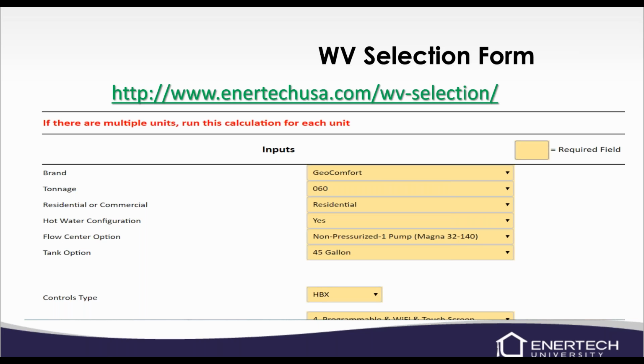We had a question: does pressurized or non-pressurized depend on what type of antifreeze is used? No, it's just whether it's got pressure on the system, pressurized versus non-pressurized. A pressurized system uses pressure in the piping so the pumps don't cavitate. So it's got to have at least a couple pounds of pressure so the pumps don't cavitate and it'll move the flow. Non-pressurized will use the standing column of water that's in that tank to basically prime those pumps.